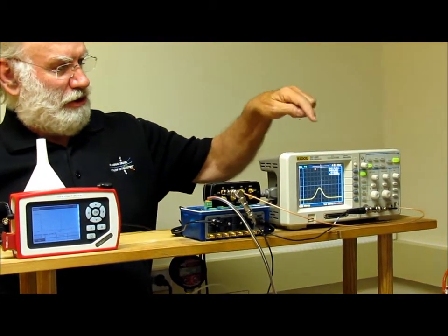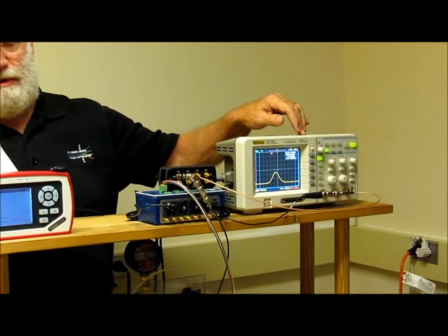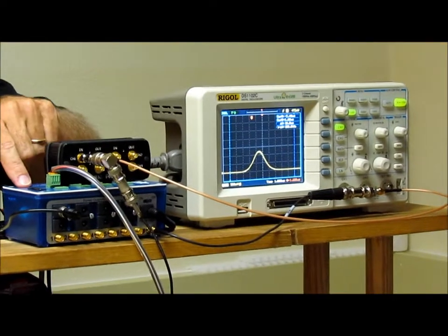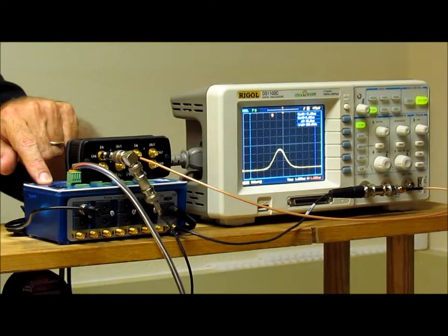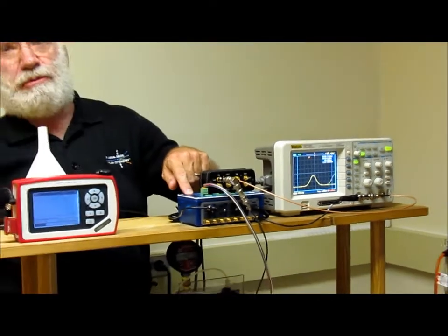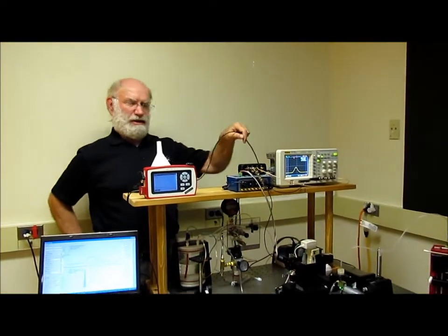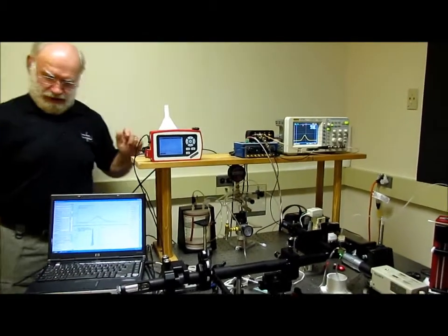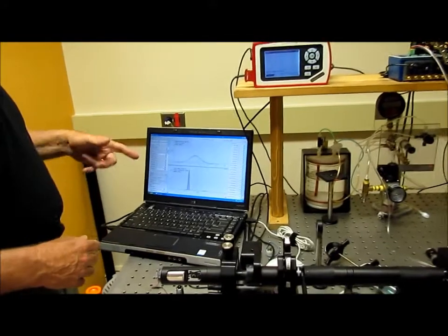they go out, and you can see the analog signals on the scope, and they also go into Azurite, which is the digital data acquisition system, where the analog signals are turned into numbers.